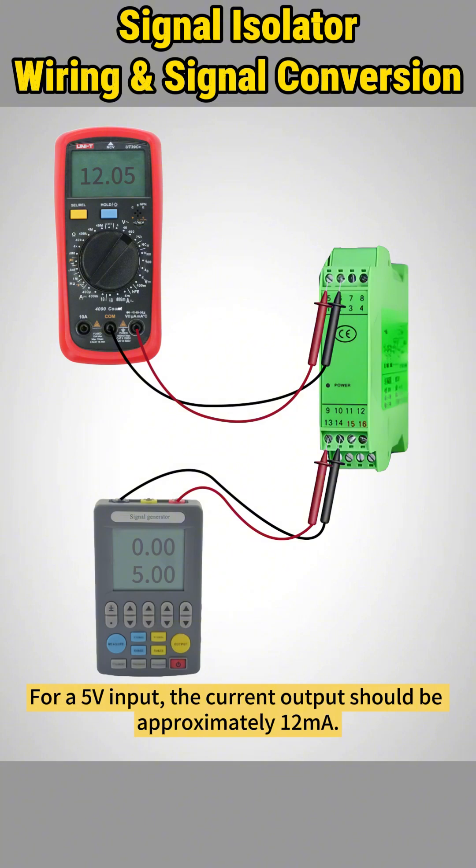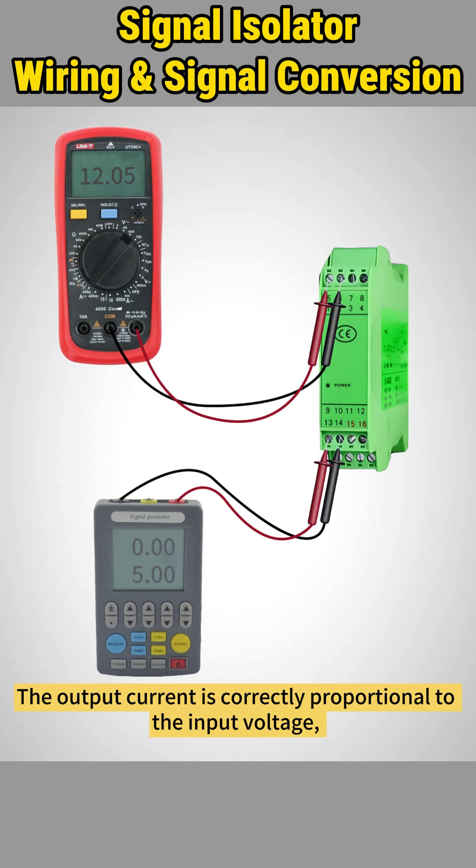For a 5 volt input, the current output should be approximately 12 milliamps. The output current is correctly proportional to the input voltage, confirming the signal isolator is functioning as expected.